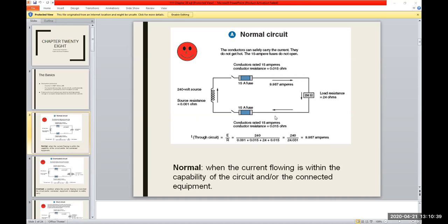And of course, you can see the conductor is rated 15 amps, so you have an ampacity, and even the fuse has the ampacity to deliver 15, but our normal operating current would be 9.987, and these things won't trip until they get 15 amps going through there.